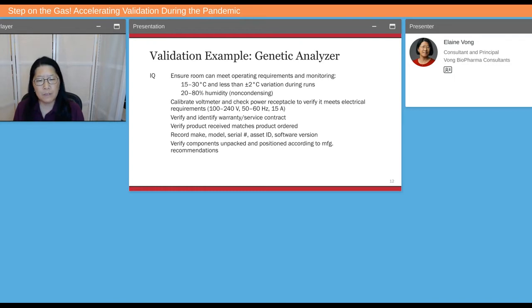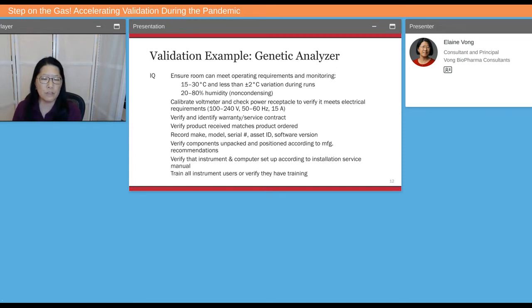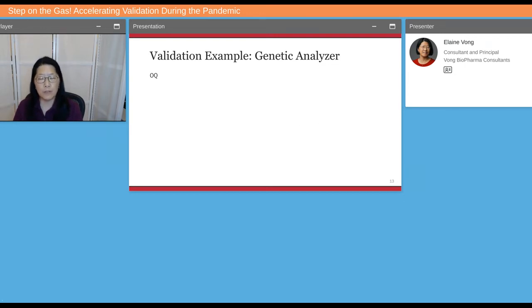Recording the make, model, serial number, asset ID, and the software version. Verifying components have been unpacked and positioned according to the manufacturer's recommendations. And verifying that the instrument and computer setup was according to the installation service manual. Training all instrument users and verifying that they do have training already.